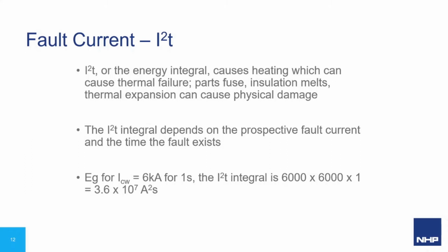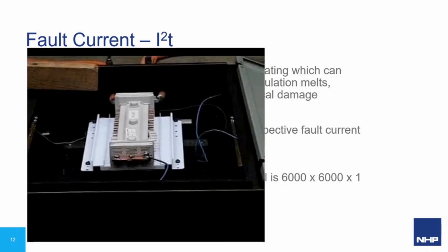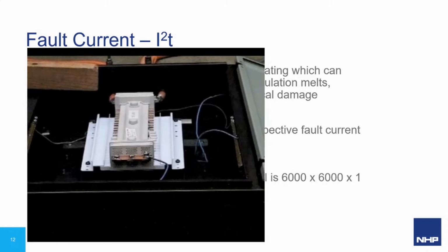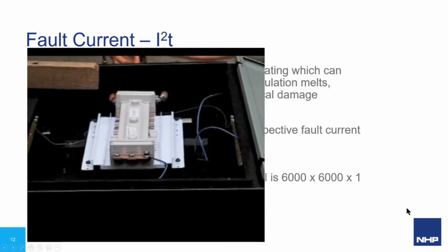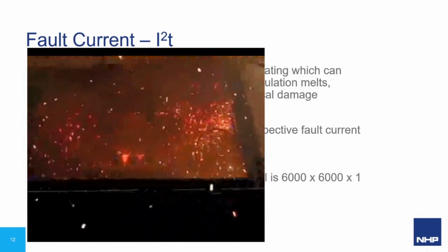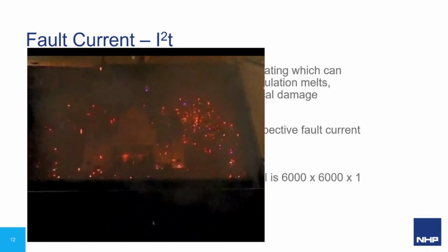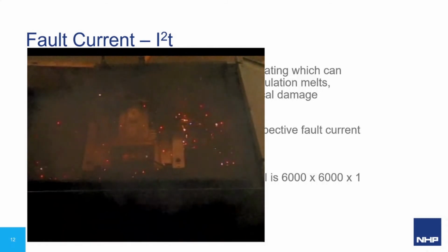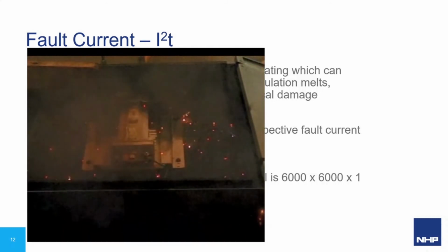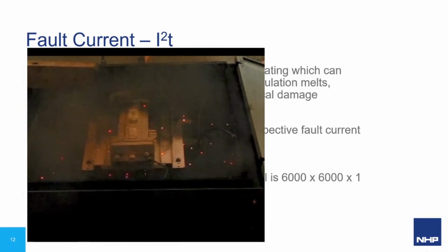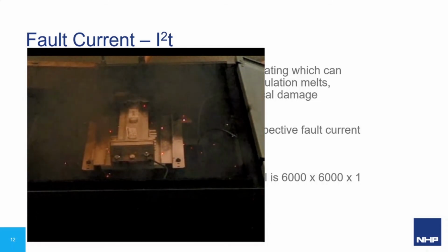The upcoming video will show what happens if the energy integral of our chassis is exceeded. You can see from that video why it's very important to make sure we get this selection process correct. The time, or the T, of our calculation is best reduced by employing protection devices upstream of our equipment that operate in milliseconds rather than seconds.